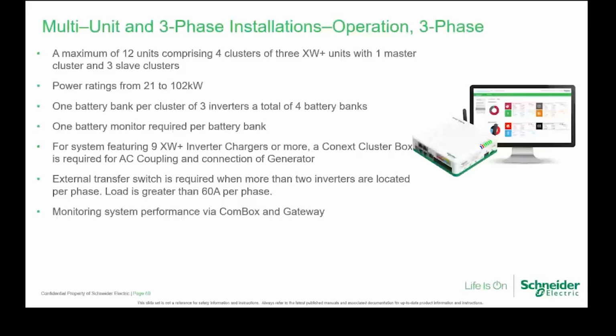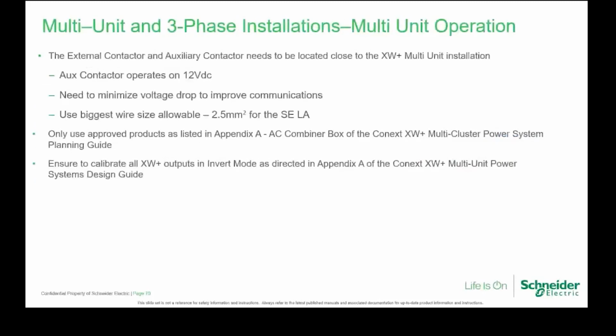Then there is the external contactor. If you require an external contactor, it needs to be as close as possible to the XW Plus units because they operate on 12 volts DC. So you need to minimize the voltage drop to improve communications. Otherwise, if the XW inverter doesn't know the status of the contactor, it could actually damage the XW Plus. Use the biggest wire size allowable, 2.5mm². Use only approved products listed in Appendix A, the AC combiner box of the XW Plus multi-cluster power system planning guide.